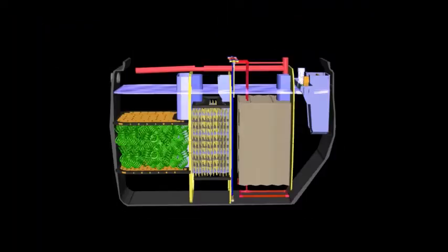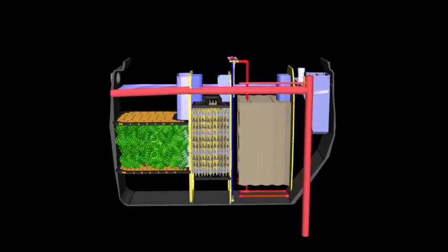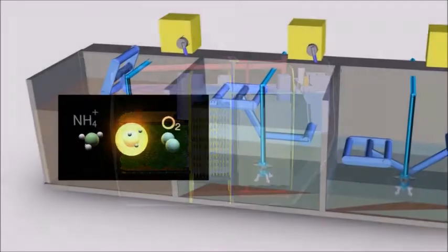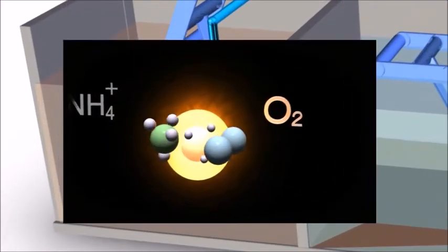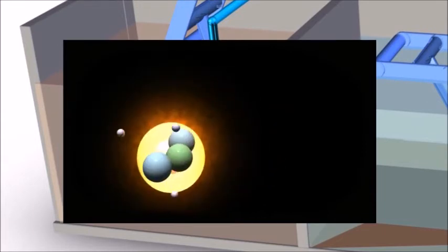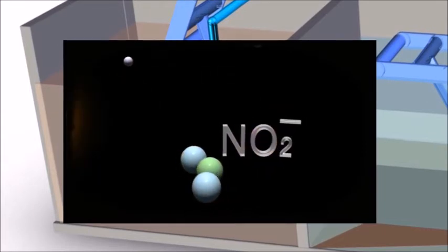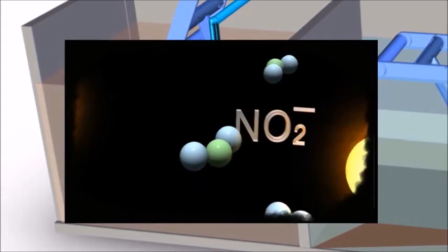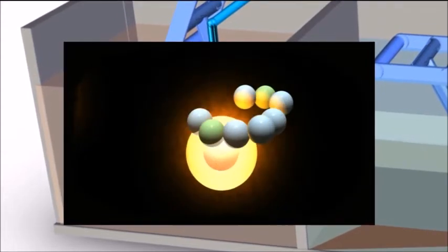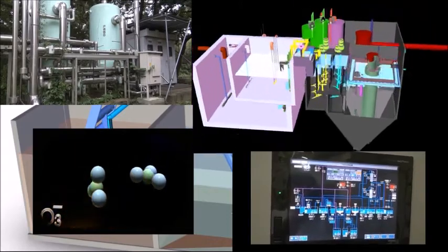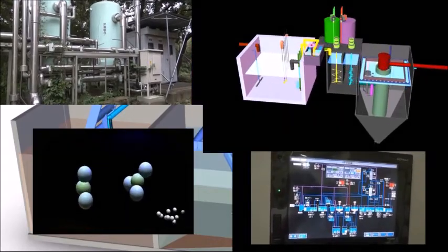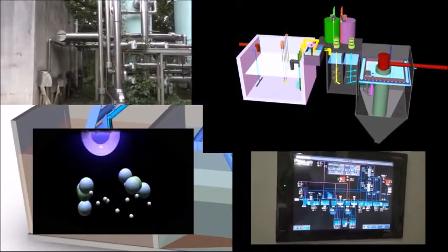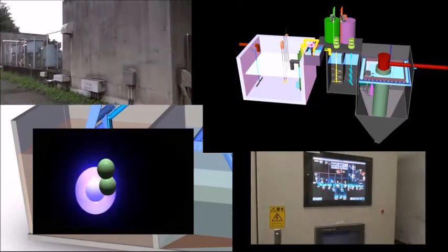Circulation of the wastewater for nitrogen removal. The tertiary treatment device includes various treatment processes: a biological reactor to remove nitrogen, a filtration equipment to remove solids, chemicals to separate polluted matters, and a tank with activated carbon in which the organic pollutants remaining in the water are adsorbed and removed.